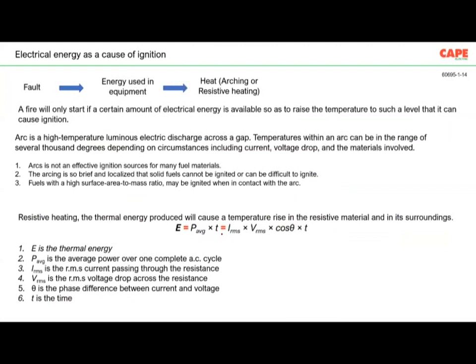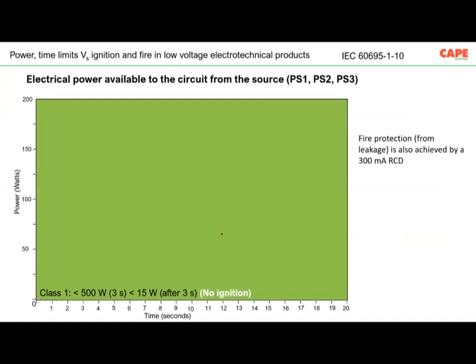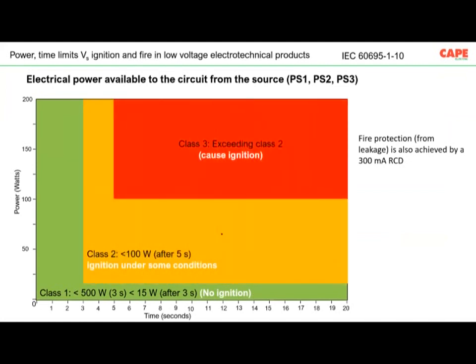Now, how to get rid of fire in electrical appliances? The power sources are classified into three with respect to fire. Class 1 power source means a power source which is unable to create a fire condition. Here, the power is in watts. So what is power? Power is nothing but the power consumed by your equipment, or the power which is going to create heat whenever there is a fault or whenever there is an arc. So this particular power, irrespective of the maximum limit, where I have put 200 watts as the maximum limit, actually it's irrespective of the maximum limit. If the fault is reduced to less than 15 watts after 3 seconds, so here, within 3 seconds, the fault energy is reduced to 15 watts. This is called power supply class 1, which is not supposed to ignite a fire.